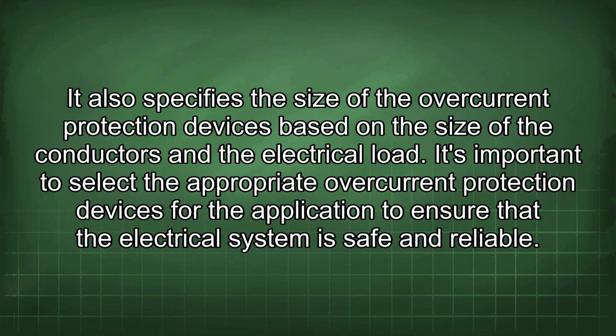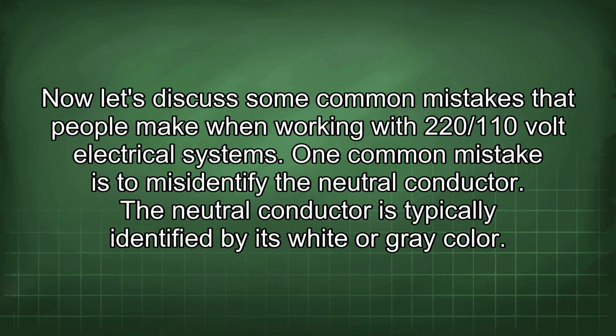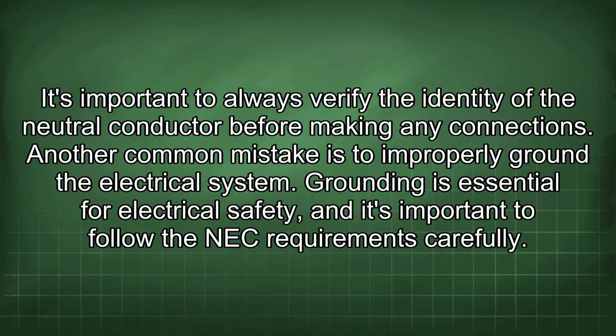It's important to select the appropriate overcurrent protection devices for the application to ensure that the electrical system is safe and reliable. Now let's discuss some common mistakes that people make when working with 220/110 volt electrical systems. One common mistake is to misidentify the neutral conductor. The neutral conductor is typically identified by its white or gray color. It's important to always verify the identity of the neutral conductor before making any connections.